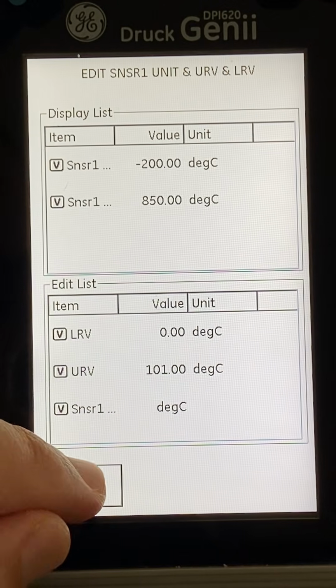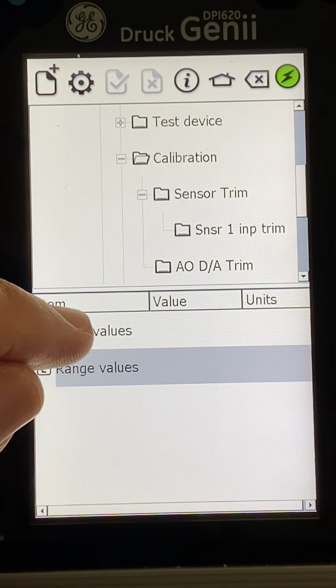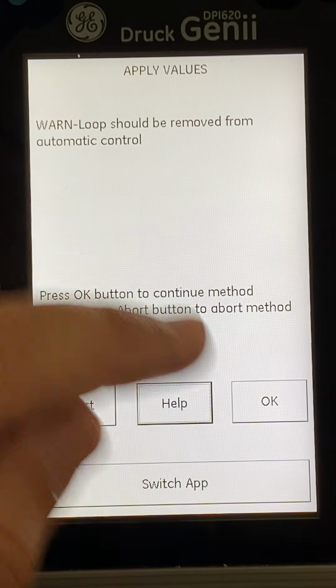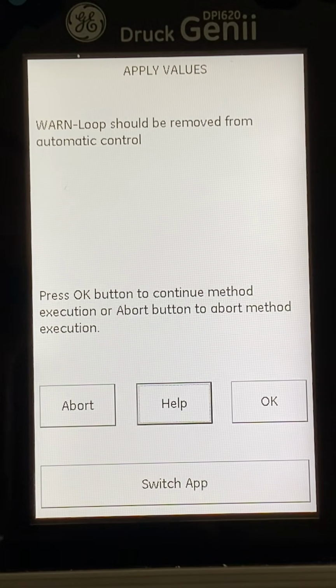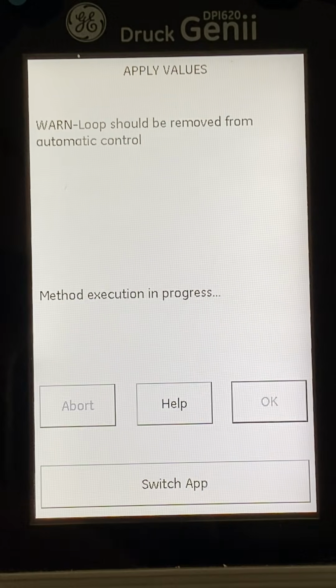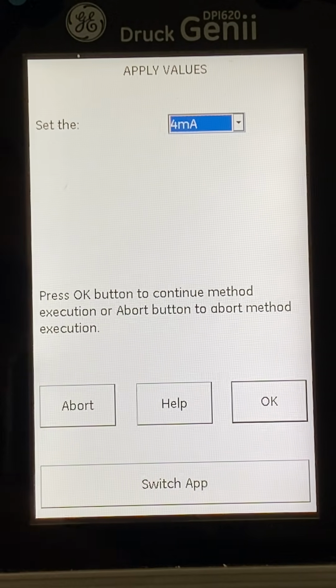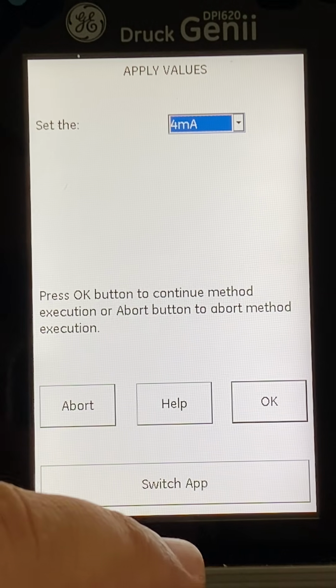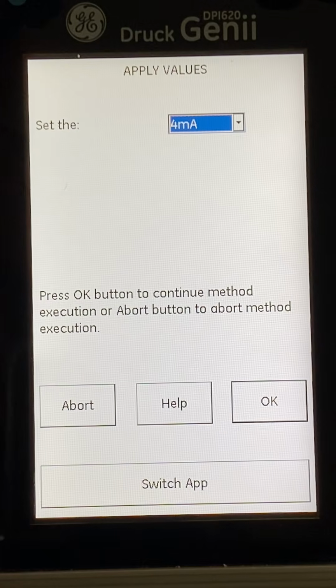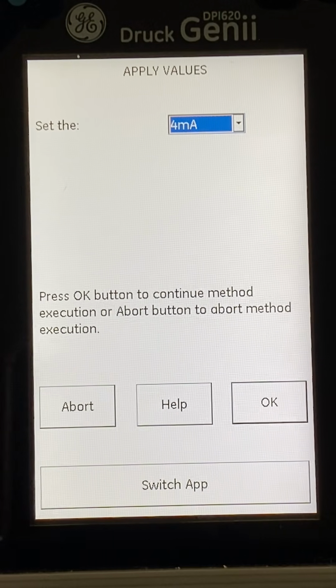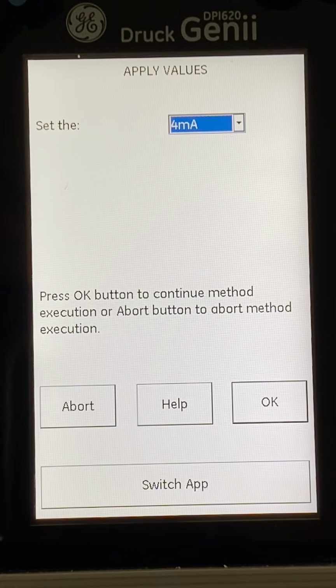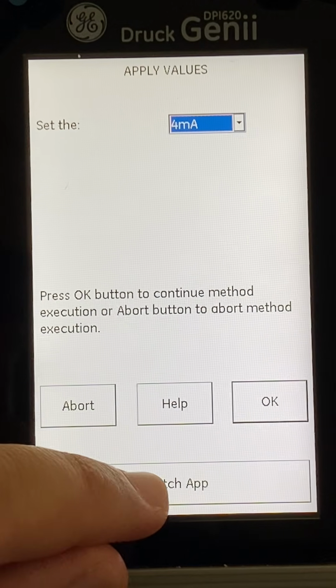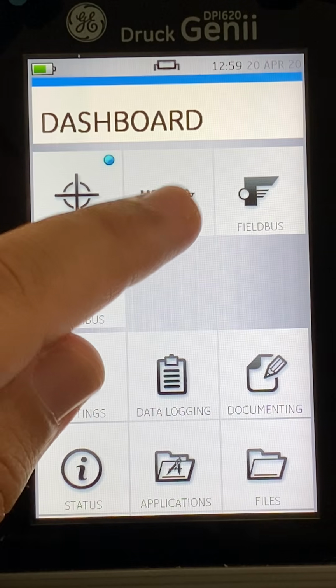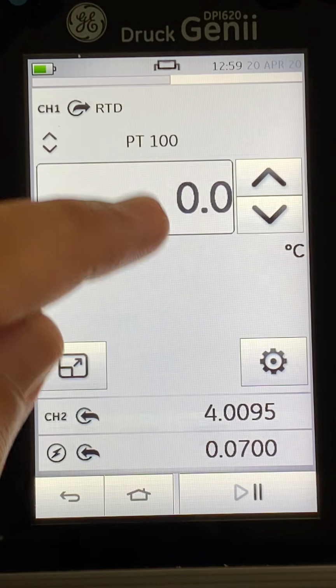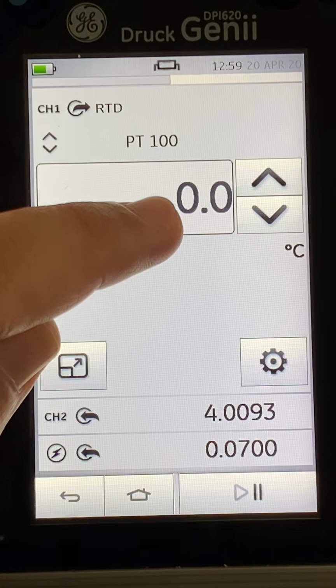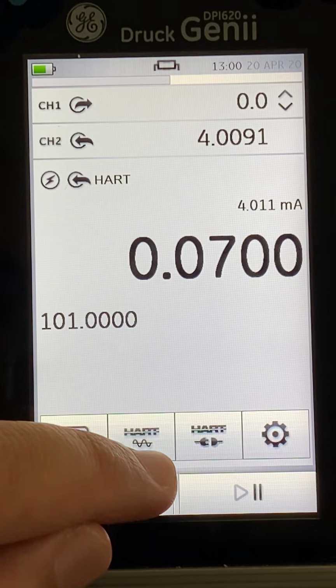I can also change the unit from here, but I'll show you how to do it in a different way. So I can apply values. It will give me a warning that this will remove the device from the loop control. That's fine. So set the 4 milliampere. I have to set the 4 milliampere now. So I will set up the input, the RTD input, which is equivalent or relative to the 4 milliampere. So I will set it to 0. It's already set to 0. Back to the HART.